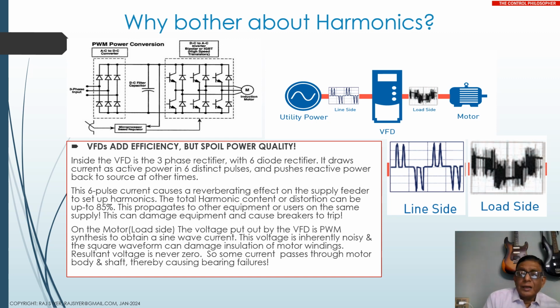And the real nuisance is that the polluted power supply available to other equipment will not be a smooth sine wave voltage. For example, if there are fluorescent tubes, power electronic controllers, or communication equipment, these will have to withstand a fair amount of interference, which is why line filters are used. It's an affair involving some calculations, but we have to curb them.